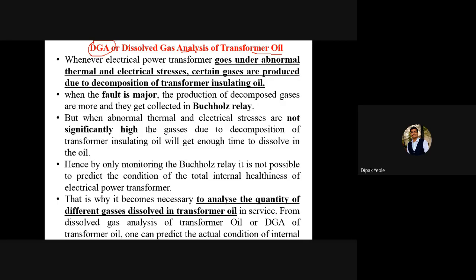Every cause has some effect. The cause here is abnormal increase in temperature, or abnormal increase in voltage or current. Because of this, when these abnormal thermal and electrical stresses are observed for the electrical power transformer, we know that there is transformer oil available which is used for the purpose of cooling as well as for the purpose of insulation. Inside this transformer oil, because of these stresses, certain gases are going to be produced due to the decomposition of transformer insulating oil.